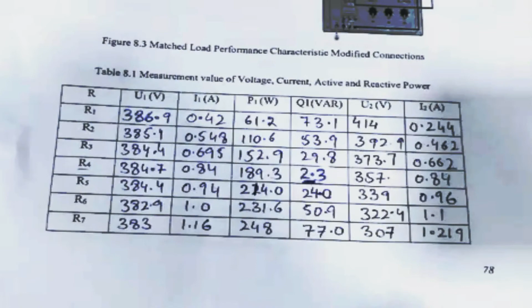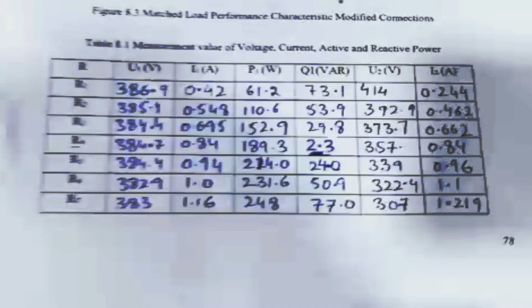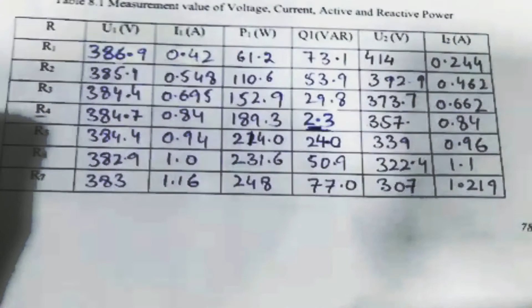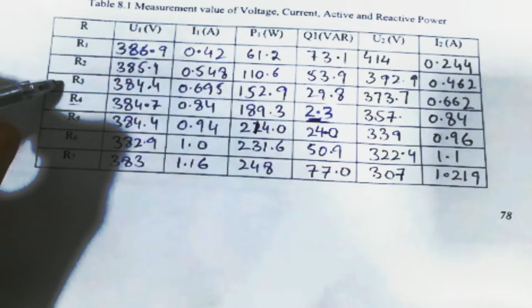Now comparing the other resistive load values, you can see from the table above the R4 values, that is from R1 to R3, we have a capacitive behavior, and from R5 to R7 we have an inductive behavior. The receiving end voltages are increasing due to the Ferranti effect, and due to the inductive behavior voltages are decreasing at the receiving end side.